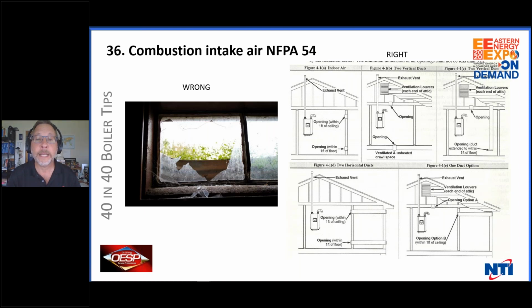And now we take into account that we're super insulating all our houses and putting in windows that are so tight, nothing's breathing. I've sat there and watched ashes be pulled from a fireplace when the boiler's running. How crazy is that? Please use outside air when you can. And if not, follow your NFPA 31, your NFPA 54 guides on how to do it. No manufacturer can break code.